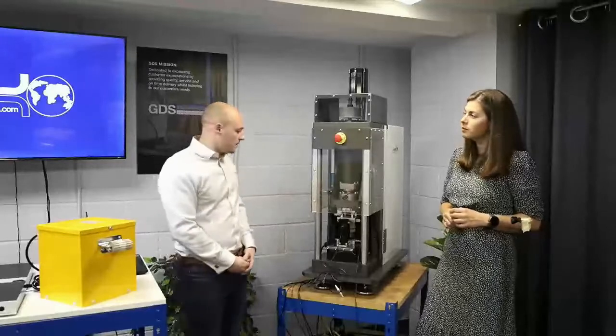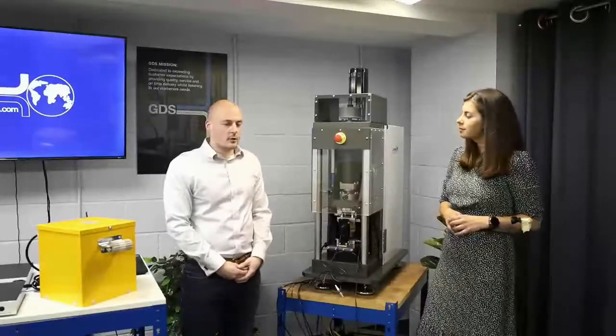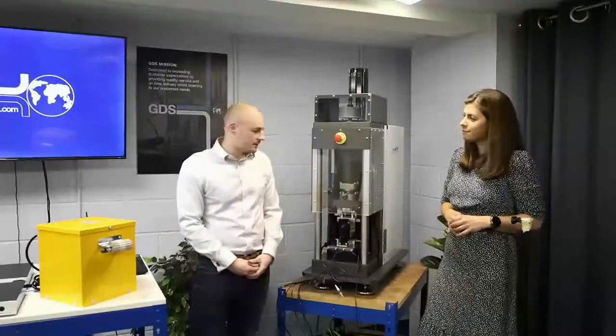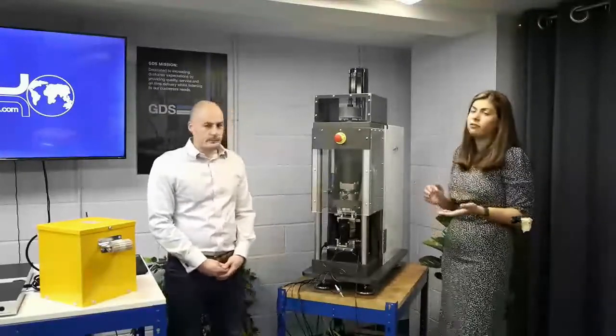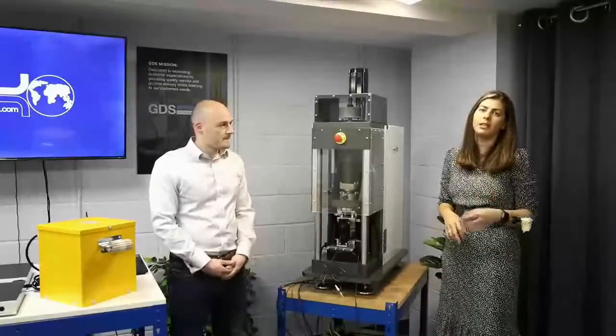It has capabilities of small strain amplitude around 0.005% and then up to large strain of 10% shear strain. It also does extremely accurate quasi-static testing. It's also available as a 5 Hz 10 kN configuration and can accommodate samples from 38mm to 100mm. And also we've now got it so it can take 150mm samples without altering the configuration. You can also upgrade to bender elements on any samples over 50mm and also do direct shear upgrades.